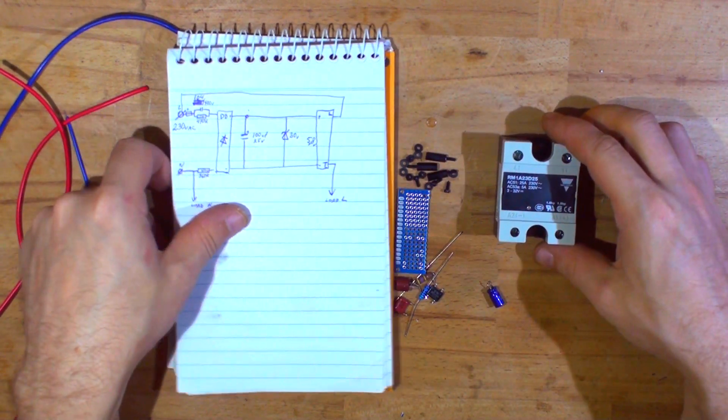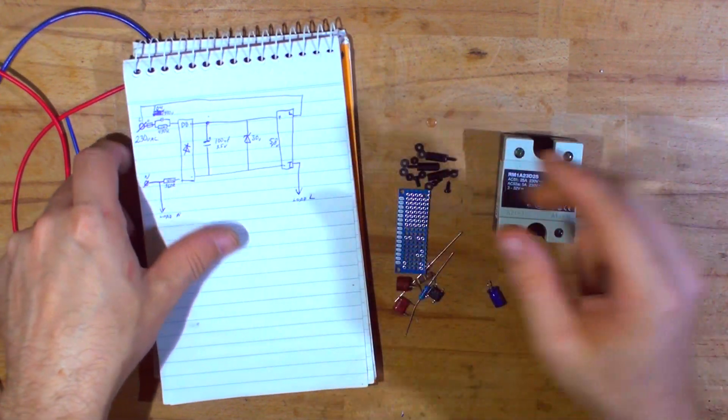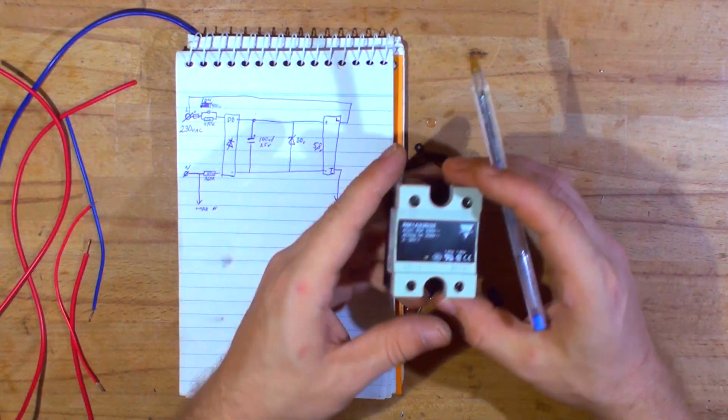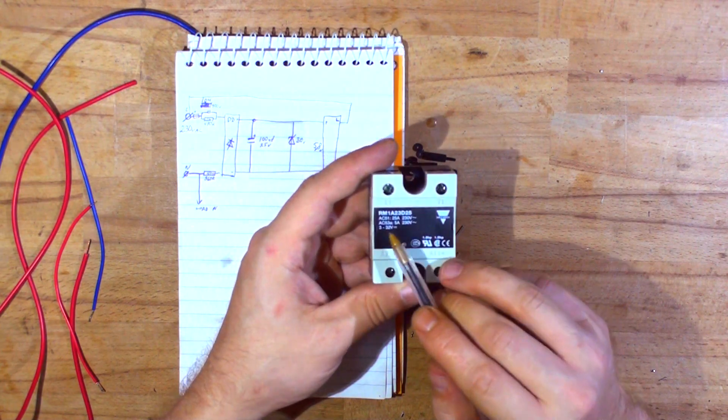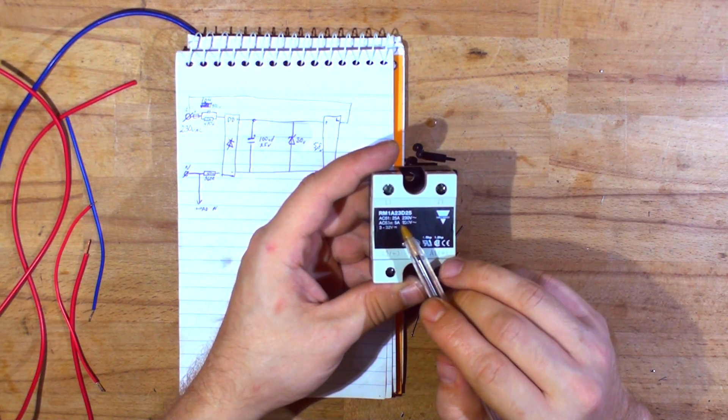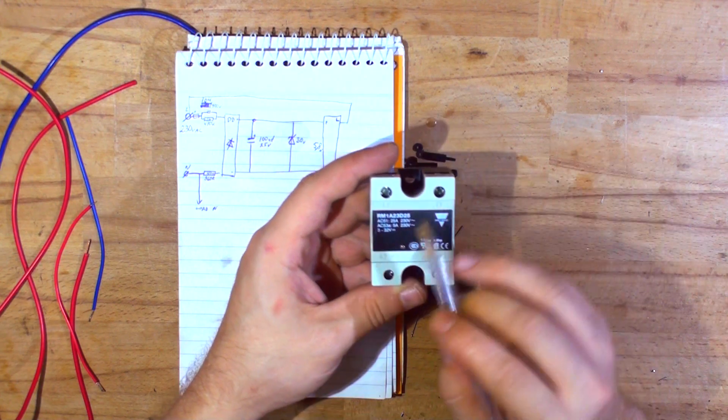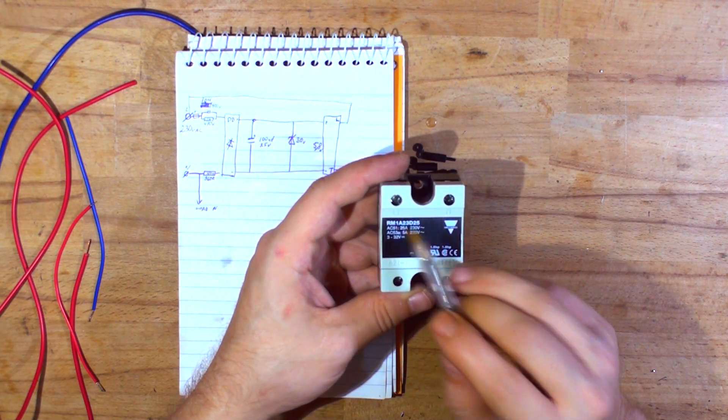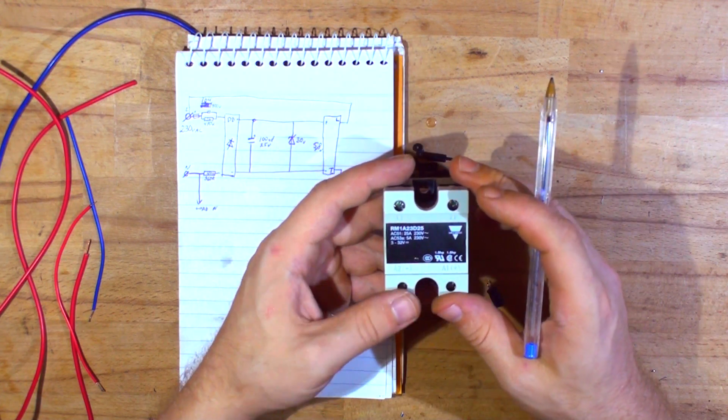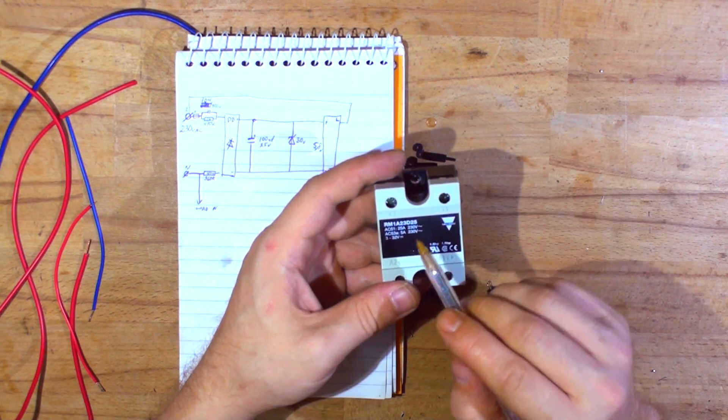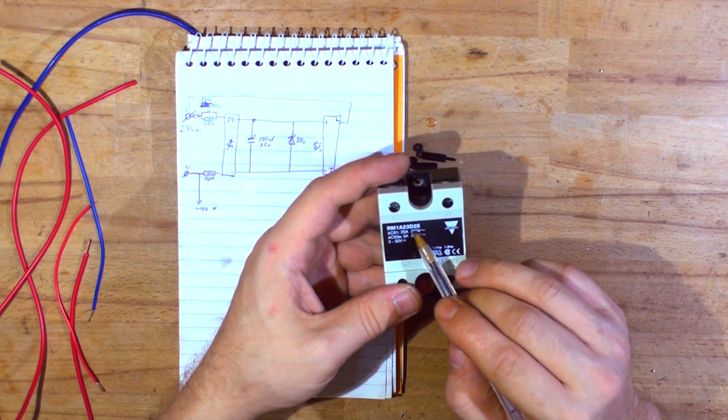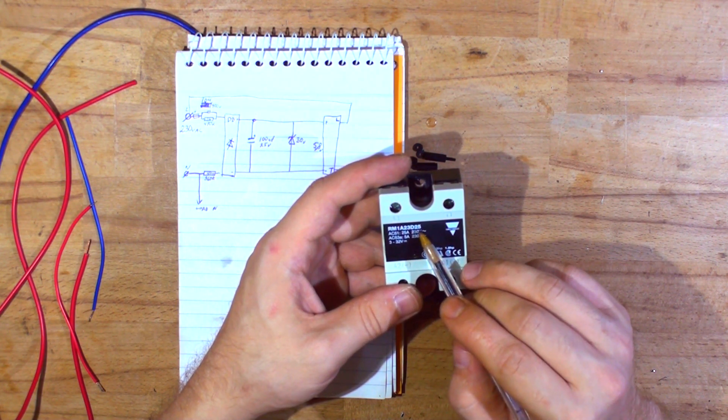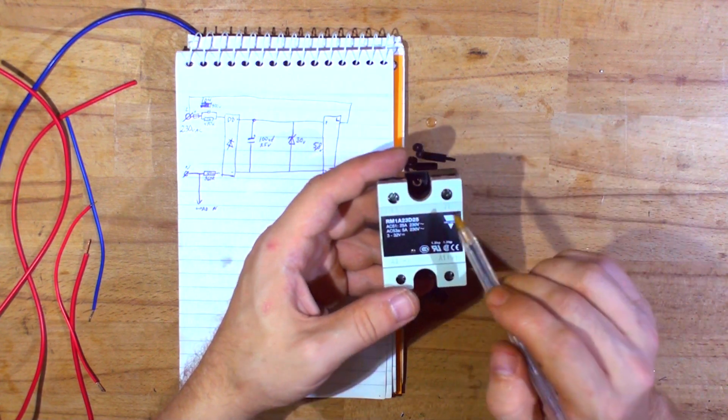The design uses these relays - some of them turn on at the zero crossing and some at random. That letter A means it's going to turn on at zero crossing, the B one is usually random. So this is a single phase 230 volts, the D means it's 3 to 32, and 25 is amps.